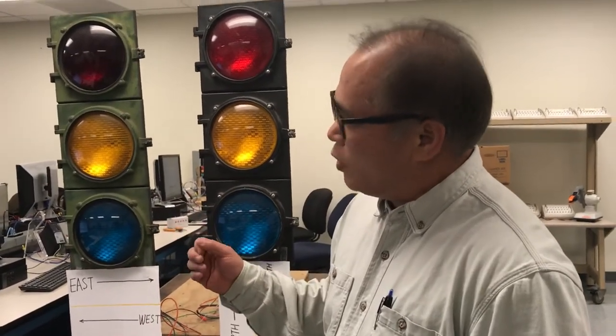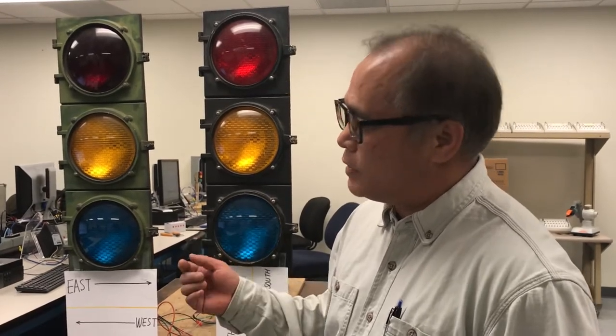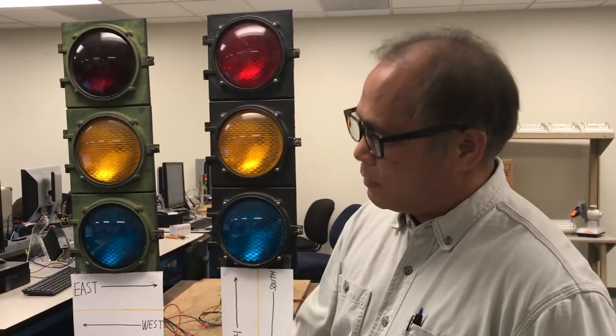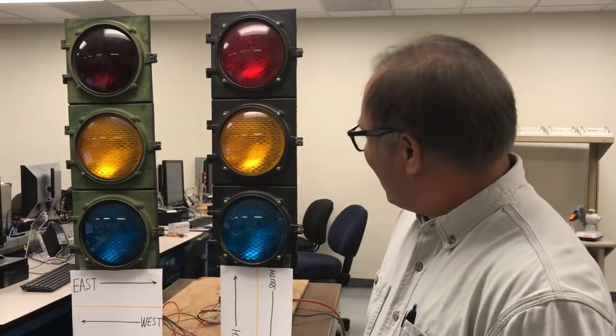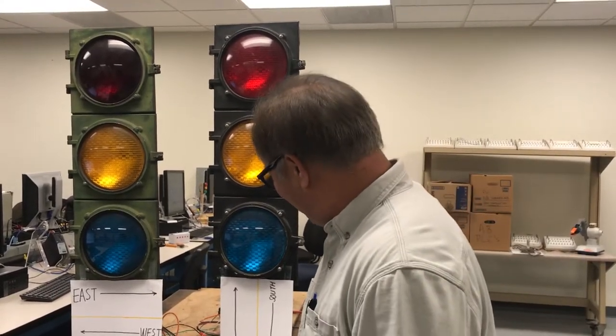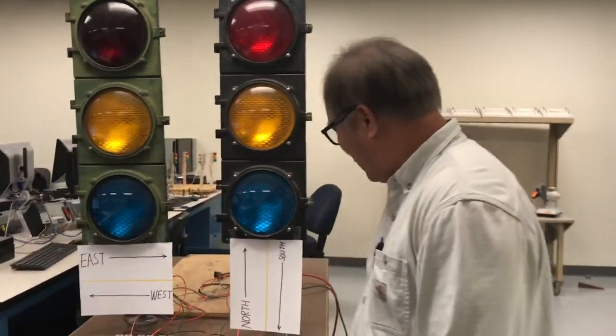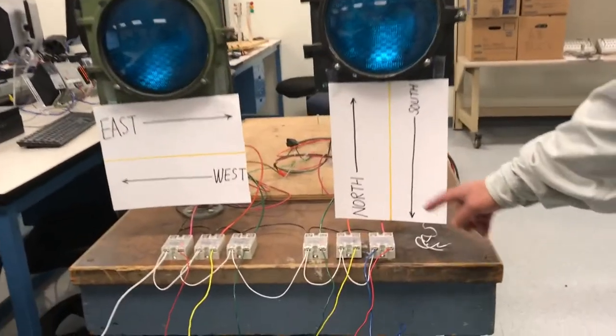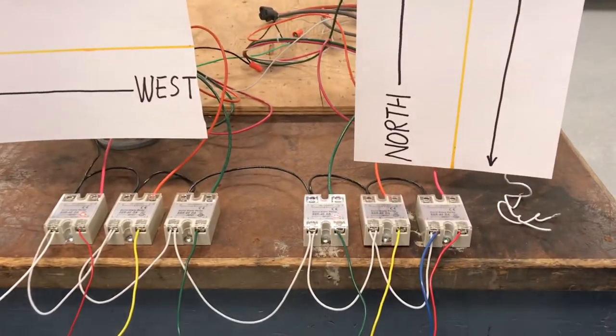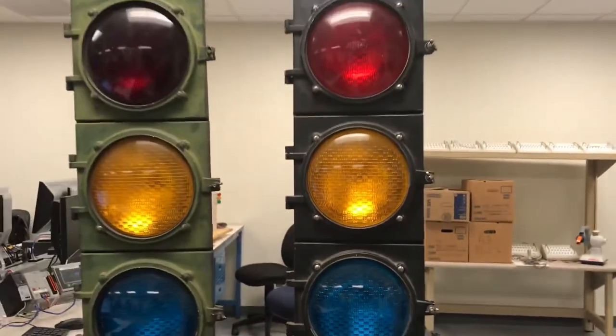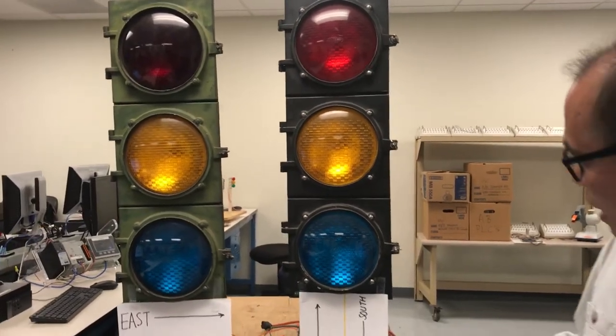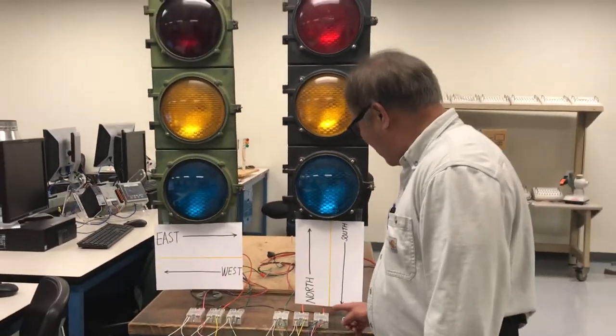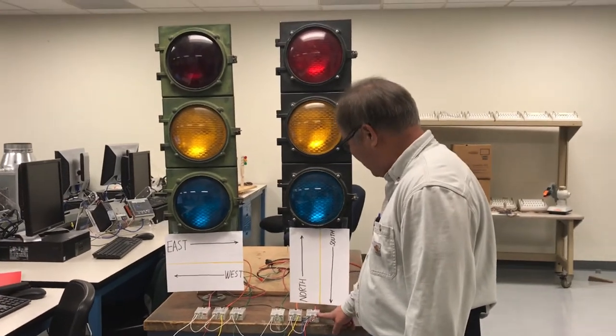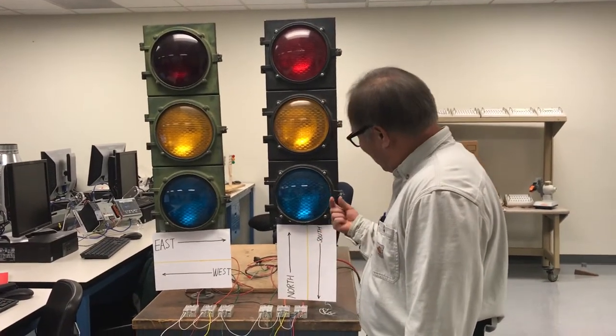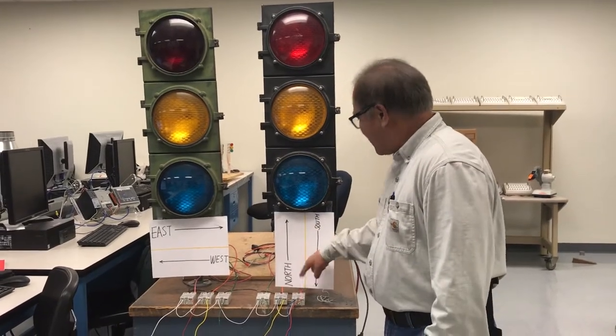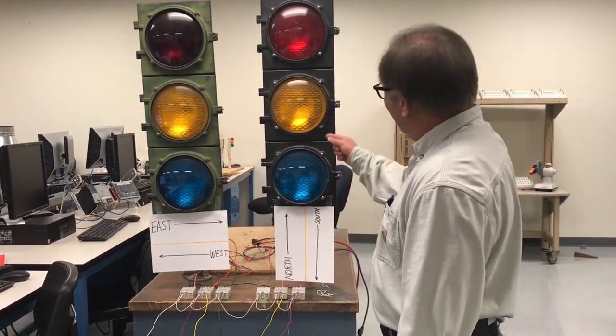I use Allen-Bradley Studio 5000 to program an Allen-Bradley PLC. And I also use 6 solid state relays, normally open relays, to control the lights here. When we apply 24 volts DC to the input of this relay, it closes the output and passes the 120 volts to the light and turns on the light.